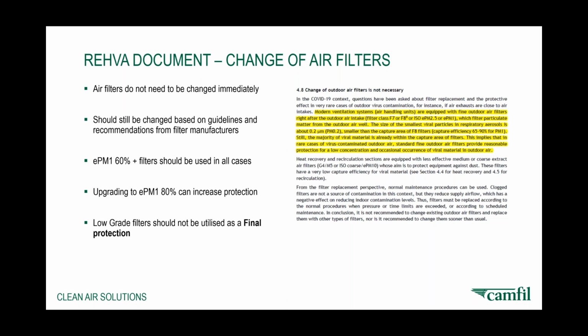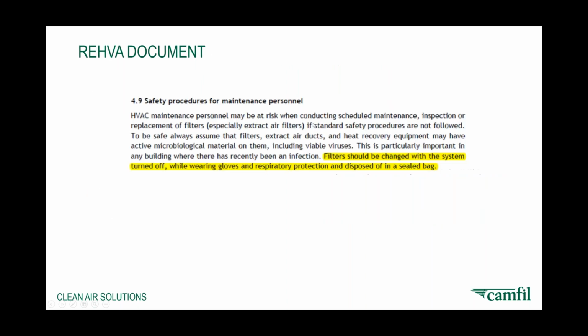They're also recommending that during the change of air filters, we look after the people that are actually changing them. So during the change of filters, in section 4.9 of the safety procedures, they're saying that filters should be changed with the system turned off. The people changing the filter should wear gloves and further respiratory protection, and then all these filters should be disposed of in a sealed bag. The reason for that is that you've got to bear in mind that you're actually catching the particles and catching possible virus on those particles going through the system.